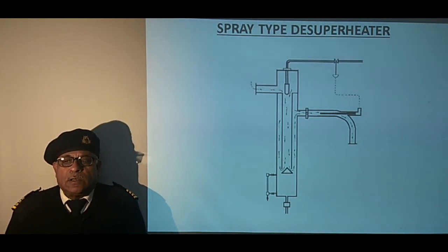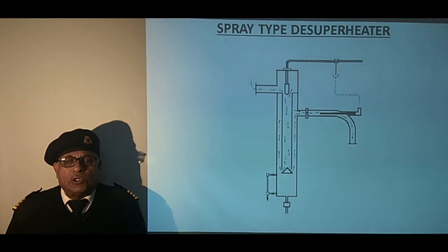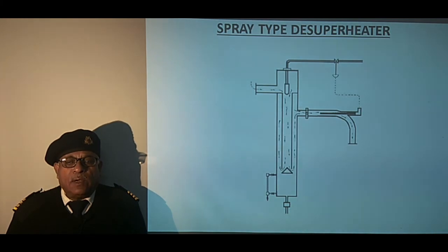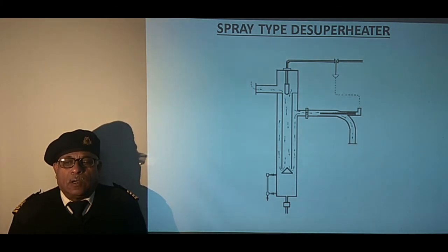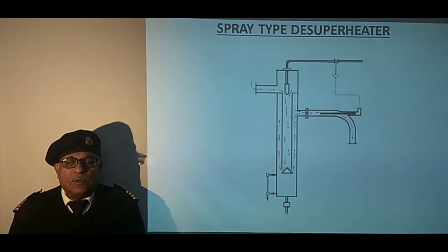This sketch shows a spray type de-superheater in which the heat exchange between steam and water takes place by direct contact. This type of de-superheater is used where a large amount of de-superheating is required. Let us see the components of the spray type de-superheater and the flow of steam, sprayed water, and condensate.